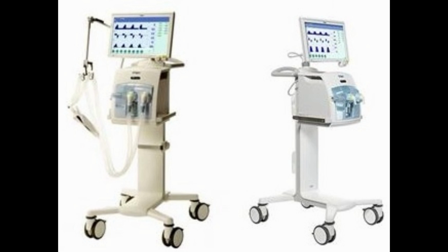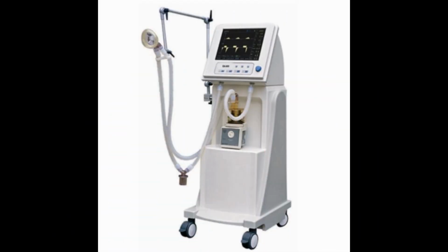The 10th thing which is mandatory to be done is to check if the battery is charging, and that it is fully charged after the long charge time. Also check the battery by operating the ventilator on battery mode, and if required just replace the battery. In some cases the battery cable may be loosely connected. Do not operate on battery mode for longer periods. That is recommended by the operation manual.